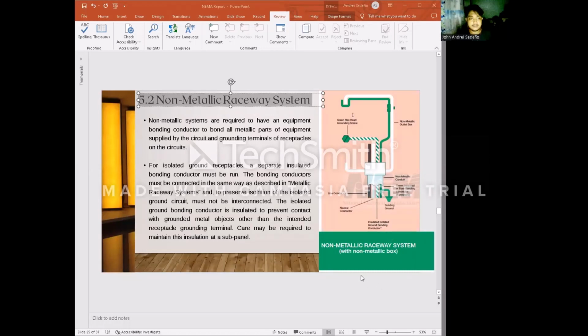Now, if you're asking what the non-metallic raceway system is, these are what you see on the surface of structures or buildings. These have coupling connectors, boxes, and fittings for the installation of electrical conductors, positioned at the top of the building, where you can see the tubes. Now, cable conduit is a subtype of raceway, perhaps the most popular one, but raceway is the more general term.